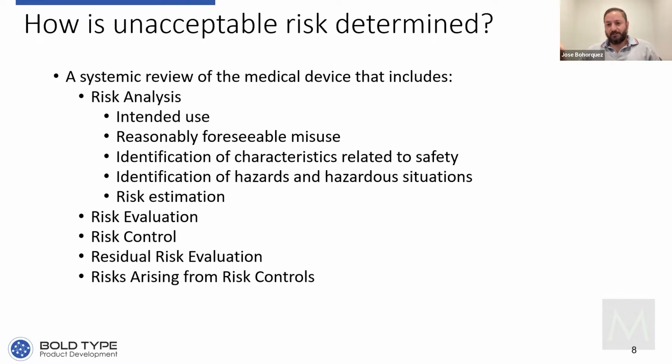That's not a formal documented means of performing risk analysis. So you might have met the needs of the first reason why you do this. Maybe you did perform that analysis and came to a conclusion it wasn't a risk, but you didn't meet the needs of the second one, which is to protect your company by ensuring that you've documented that you're going through this process.